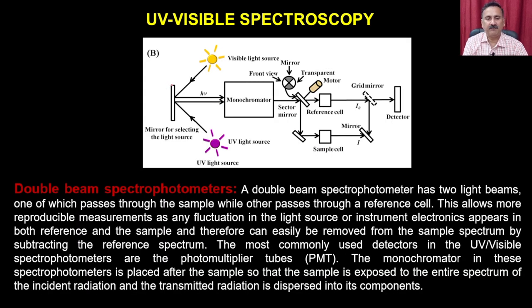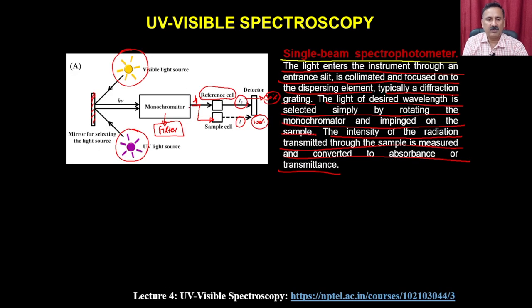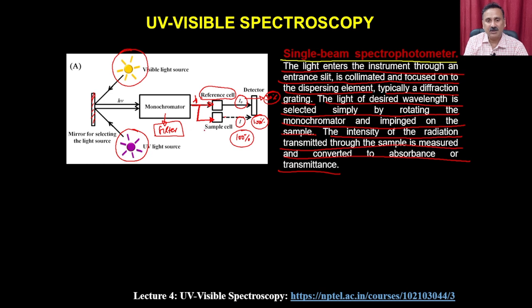In a double beam spectrophotometer, there are two actual light beams: one passes through the sample while the other passes through a reference cell. This allows more reproducible measurement, as fluctuations in the light source or instrument electronics appear in both reference and sample and can be removed by subtracting the reference spectrum. In a single beam spectrophotometer, if there is any fluctuation in the direct light, you will not be able to map or measure it — that is one drawback of single beam instruments.